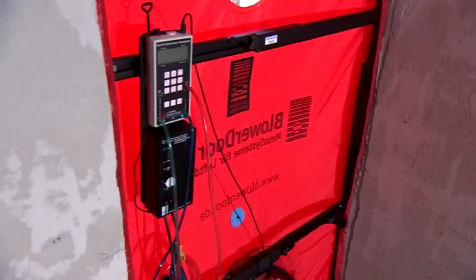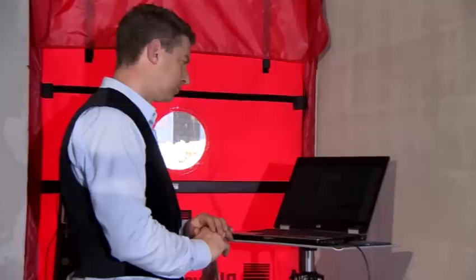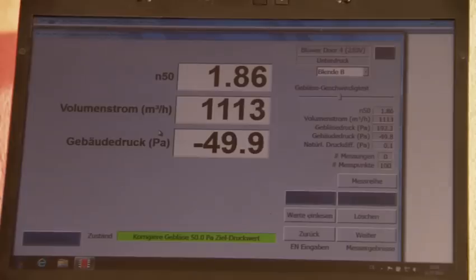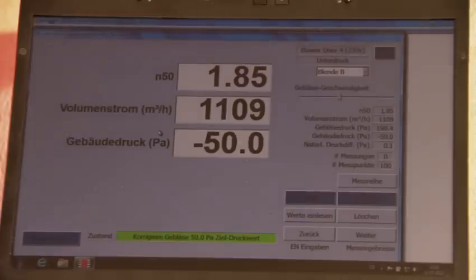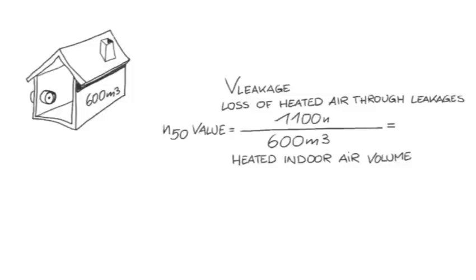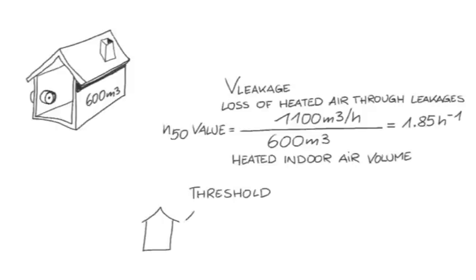In our example, the fan delivery rate is 1,100 cubic metres per hour. Hence, 1,100 cubic metres of warm air escape in case of a heated indoor volume of 600 cubic metres. 1,100 cubic metres per hour divided by 600 cubic metres results in a value of about 1.85. The air in the building has been changed 1.85 times per hour. For buildings with natural ventilation, the air change rate must not exceed 3 per hour. For buildings with a ventilation system, the air change rate must not exceed 1.5 per hour.